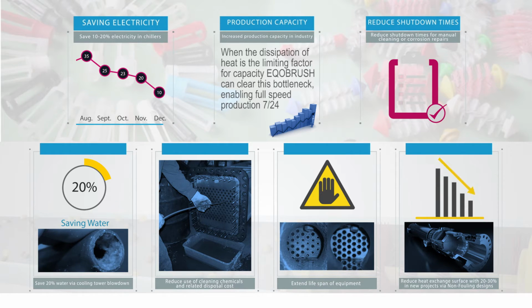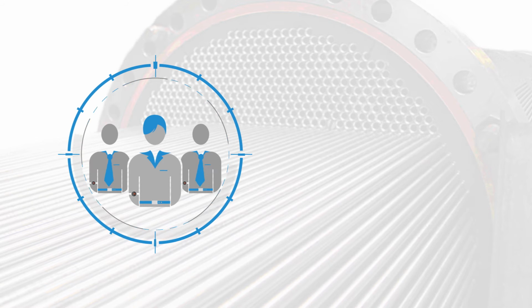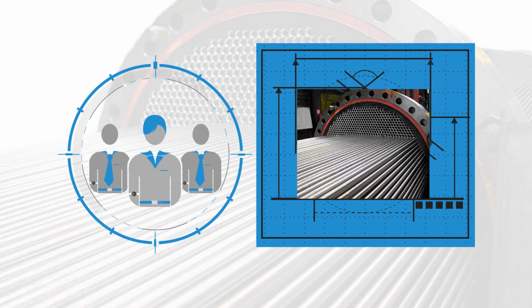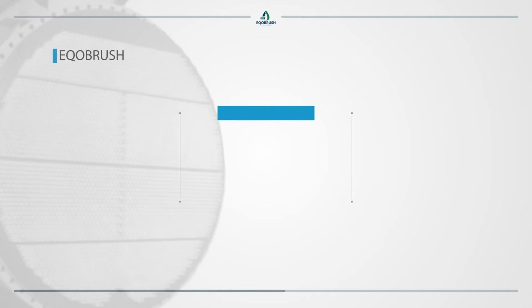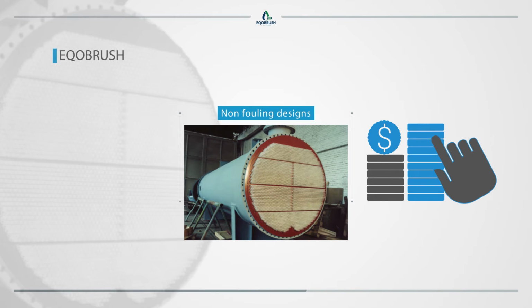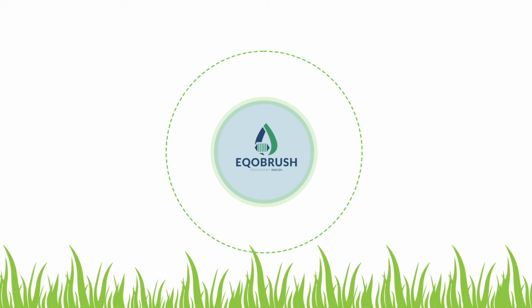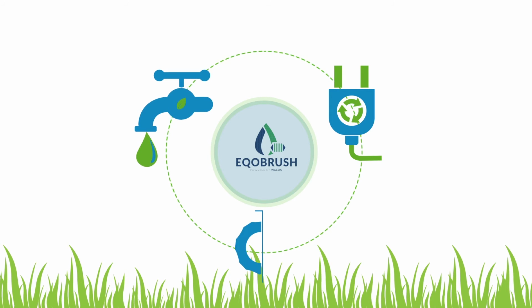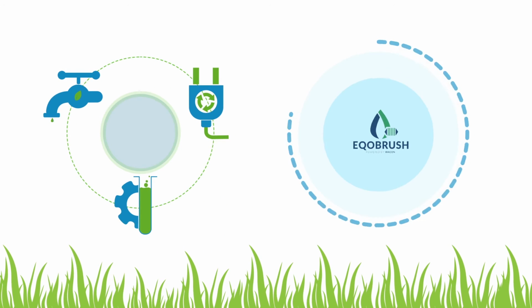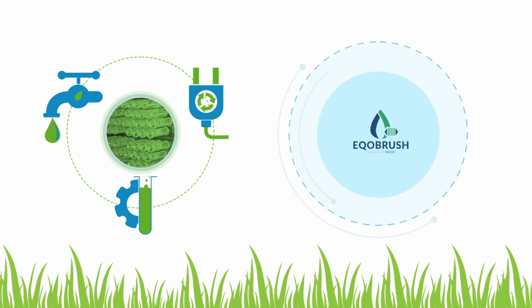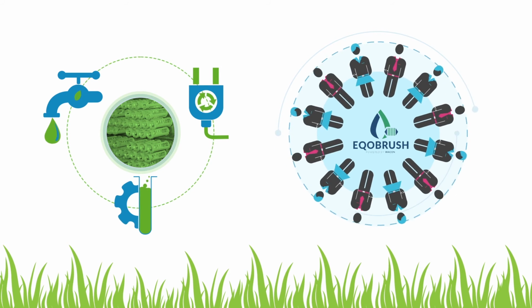Reduce heat exchange surface with 20 to 30% in new projects via non-fouling designs. Design engineers factor in the expected fouling-related efficiency loss by increasing the heat exchange surface. Non-fouling designs are limited in size and capex, therefore free up budget for investment in Eqo-brush. Advantages such as the saving of electricity, water and chemical use have a direct environmental impact. Therefore, Eqo-brush is more than a contributor to the profitability of your operation. It also helps conserving the planet for future generations.